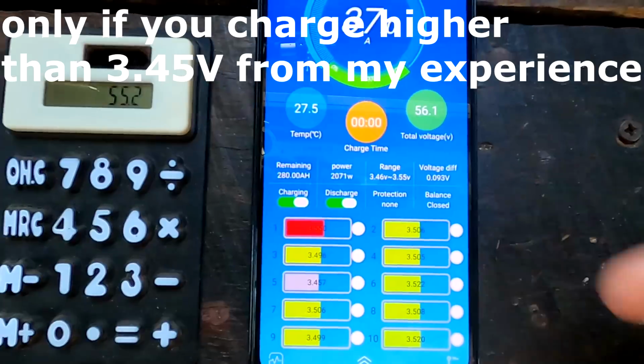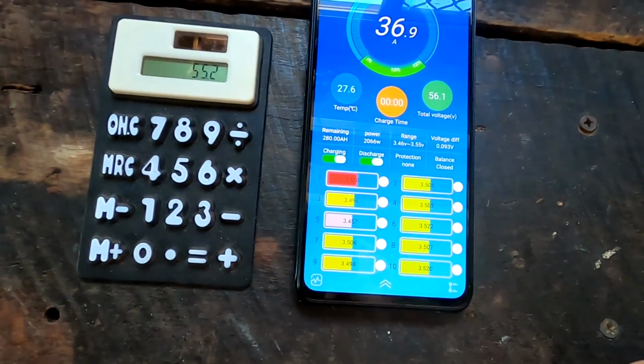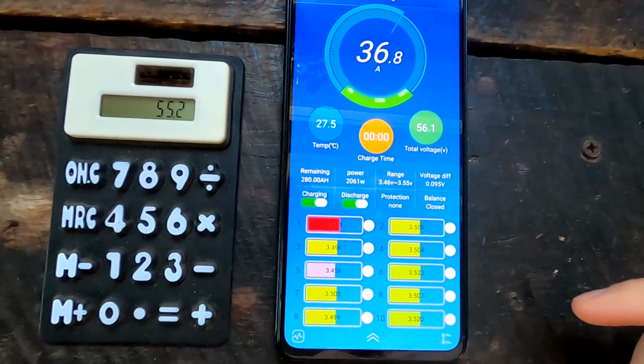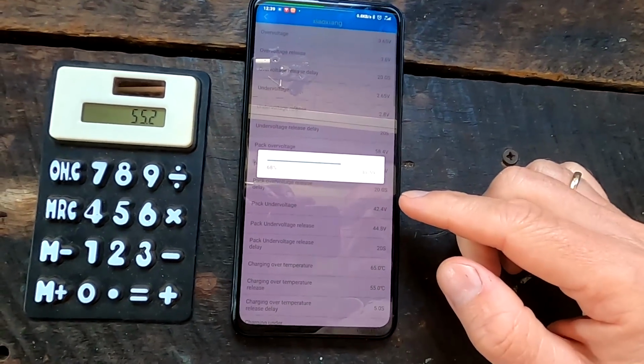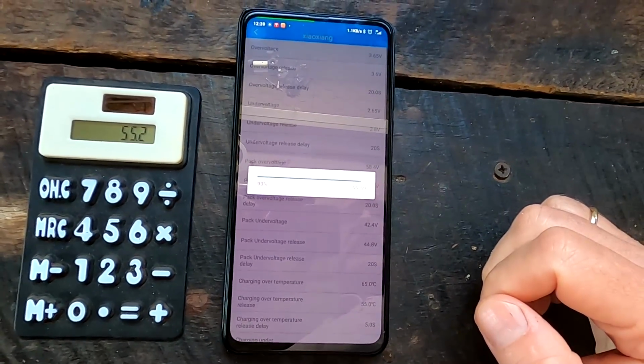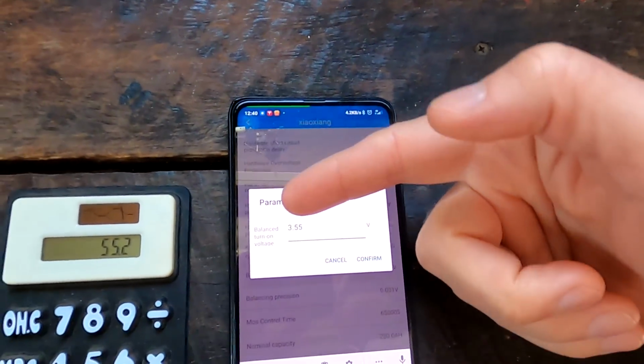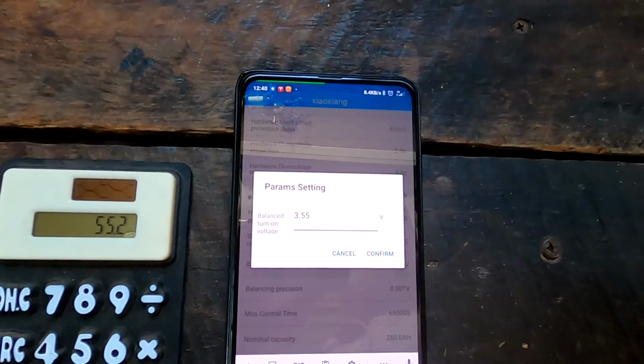We're almost 100 millivolts off now. I think we've just reached absorption voltage, 56.1. To make this all work, we need to change the balance settings in the BMS a few times as well. Ideally at this voltage, 56 volts, that's 3.5 volts per cell if they were all balanced. So I'm setting the balance kick-in, turn-on voltage at 3.55. Let's let the battery absorb for maybe 20 minutes, and then we'll have another look at the balancing.